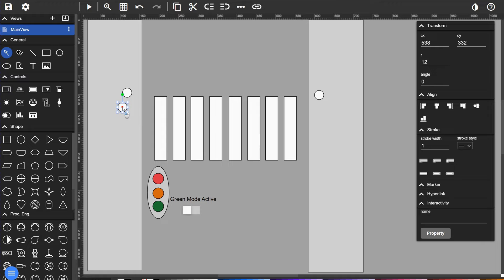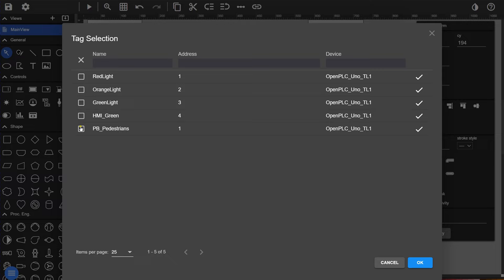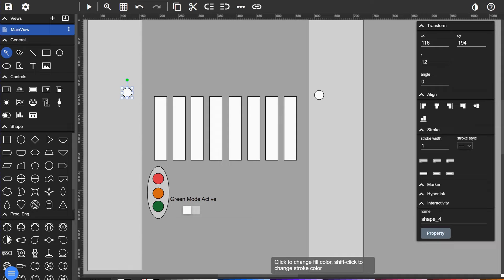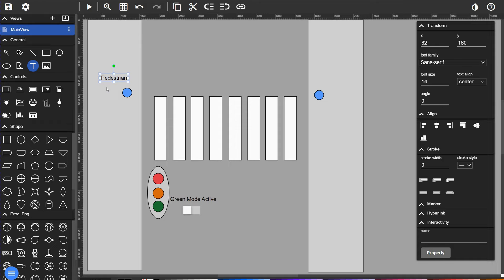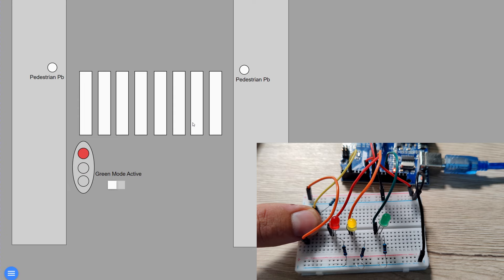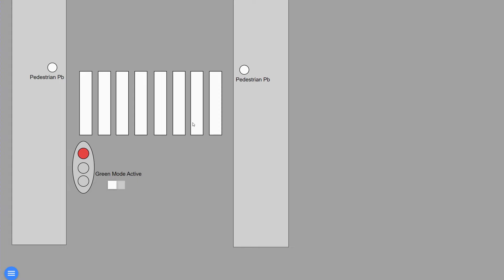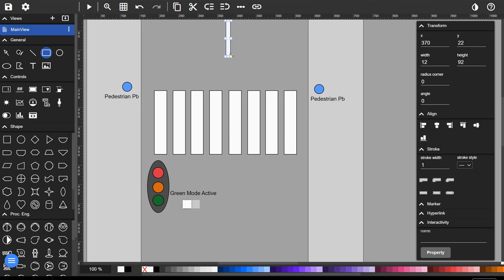We now continue to work on the pedestrian button. Knowing the button is an input is essential, so you know you cannot change it when using Modbus. You should never use a button in the HMI to visualize a Modbus input. When we run the screen we see that the buttons react as intended in the HMI. We now can polish things up to have our final screen.